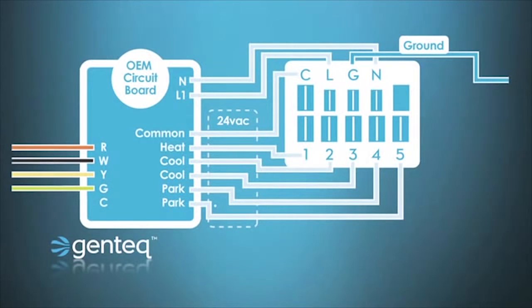If you look at this at a quick glance, you might think, well, that looks really the same as a PSC motor, other than the line, ground, and neutral connections on the motor. But what you'll notice if you look at the schematic for the system or measure voltage is that the voltage going to taps 1 through 4 is 24 volts, which is very different than a PSC motor.